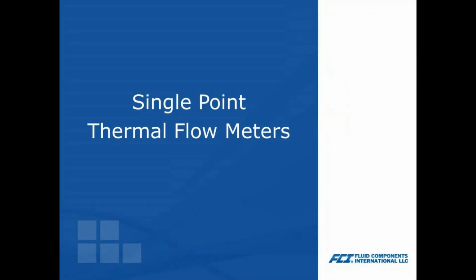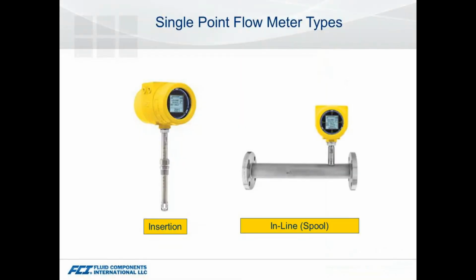So, going to break it down into a few groups. The first one is single point flow meters, and what we mean by single point is it's just one sensor in the system. And there's a couple different styles. You have an insertion type, which allows you to utilize the existing piping and ductwork. And then you have what we refer to as inline, some might look at as a spool design, where the sensor is installed in a spool piece and then calibrated in that fashion.